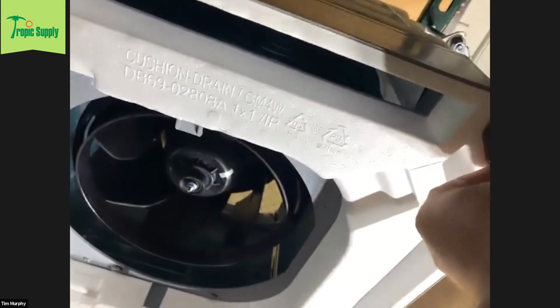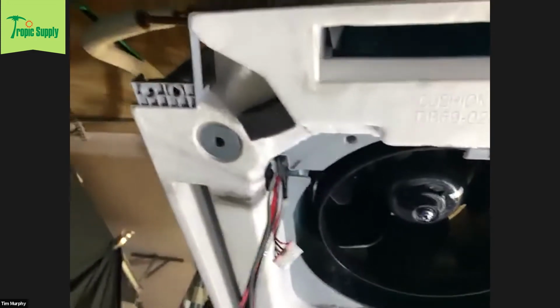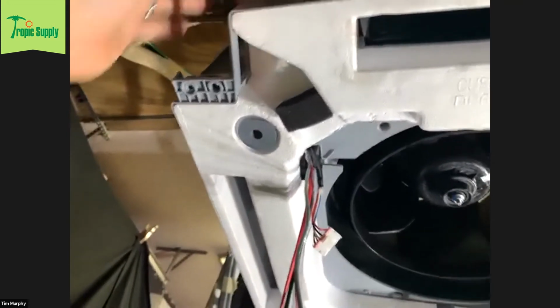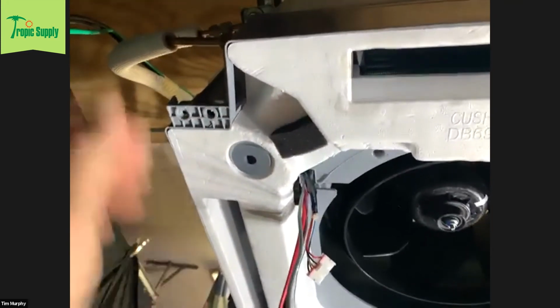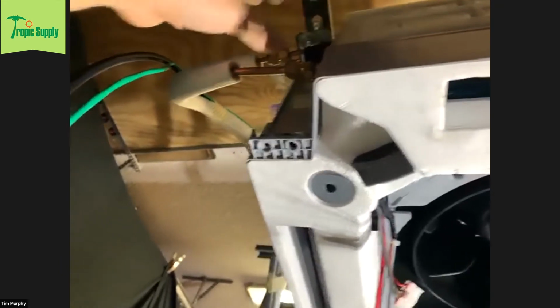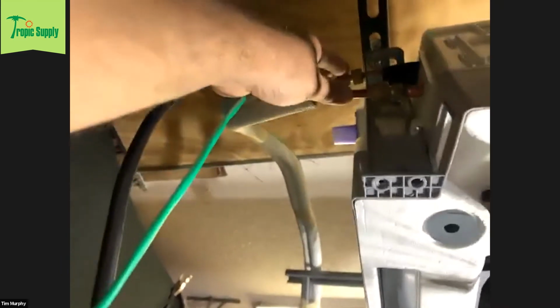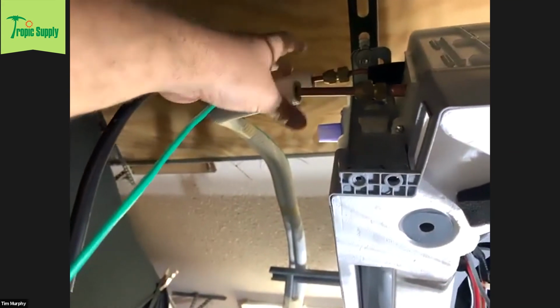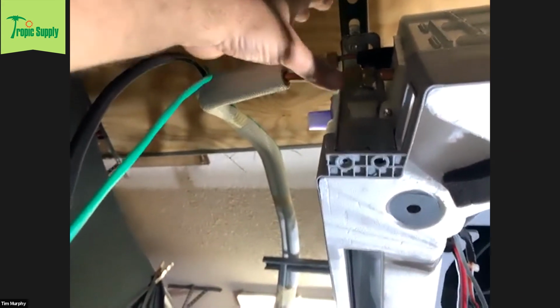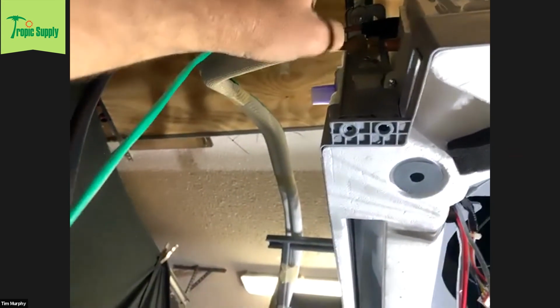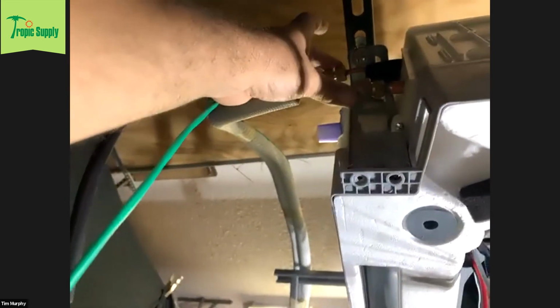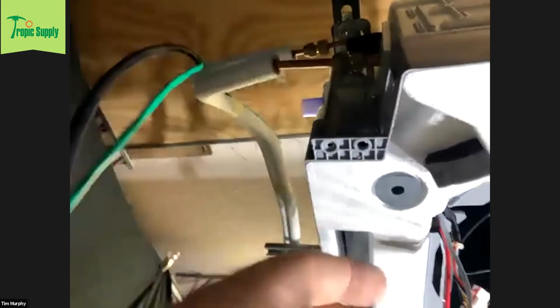The 4-way cassettes, I think, are a lot easier to work on. When you install this 4-way cassette, you can get to everything through the bottom. You really don't need to get to the top unless you're trying to do the flares. If you're putting this in a situation with a hard ceiling, you need to make sure you have access to be able to get to these flares, so you're probably going to have to put in an access panel. Other than that, you also need to be able to get to the drain line.